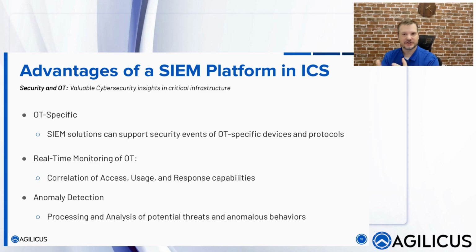When that behavior changes, for example, they try to access different sensors or different interfaces that diverge from the permissions and the set of access that they have, it will now trigger on that. So it's a learned behavior. It's not necessarily rules-based, but it's really about understanding what's the baseline of activity for an identity accessing a specific resource on my industrial control system, and being able to alert when that deviates. Think about an intrusion detection system, but with no set rules. It's simply understanding when your behavior changes.